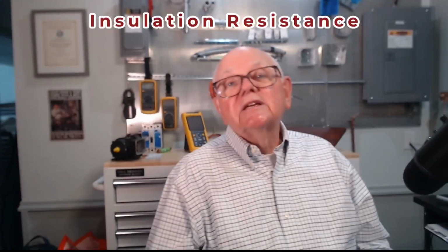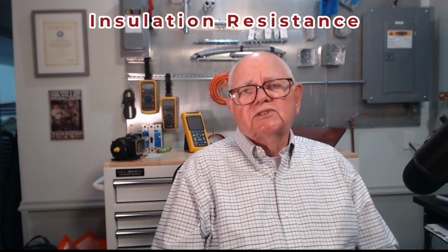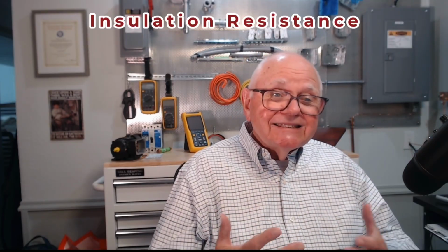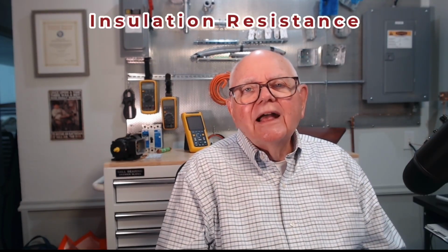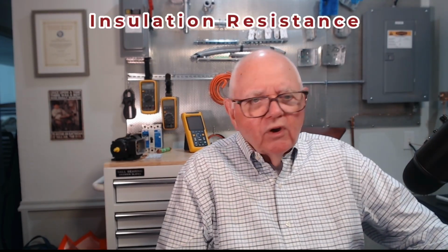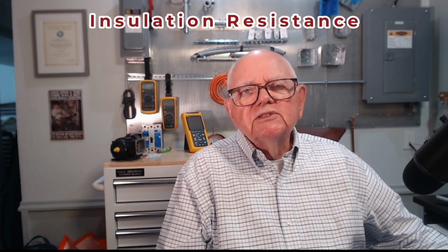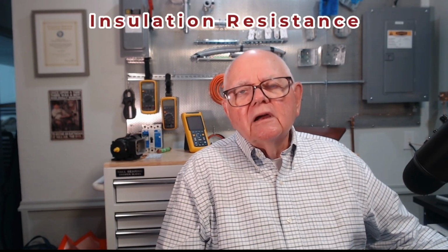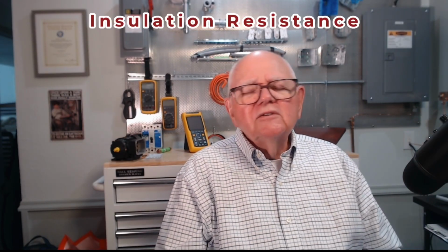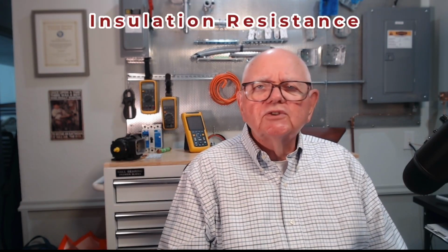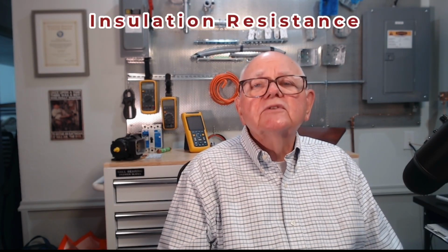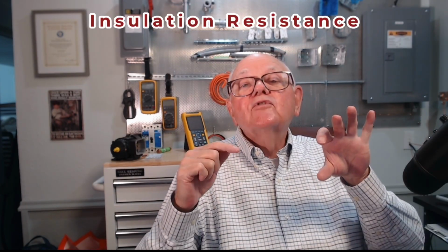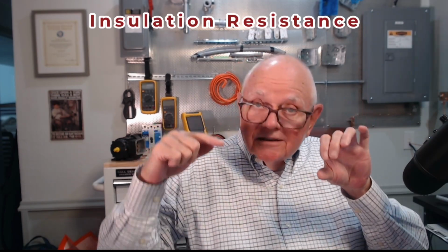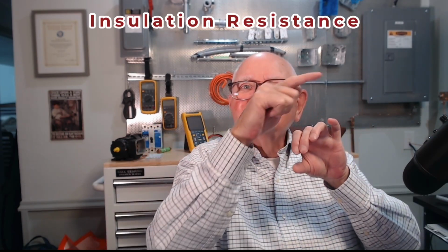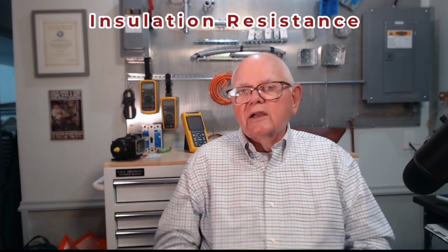Now, the next topic let's move into then is insulation resistance. It only makes sense then that insulation will fail over time. All insulation will break down. I heat it, I cool it down, depending on the type of insulation and so forth, and it begins to degrade over time. So I have to make sure that not too much current leaks through that insulation and out to the frame of my equipment.